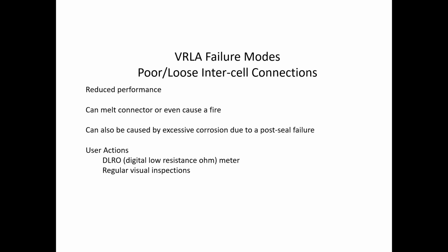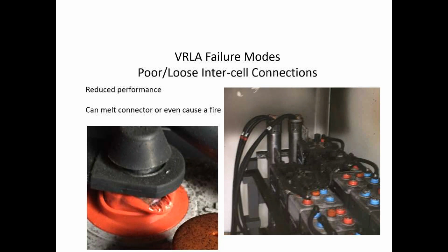So we do recommend using a digital low resistance ohm meter to check the resistance of that strap, and then doing visual checks for corrosion. This particular battery was a UPS application, so a very high rate under discharge.